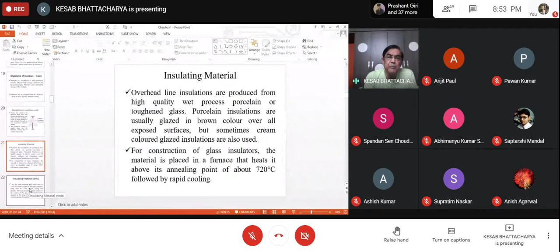And due to this process, heating it up to its annealing point and then rapidly cooling it, the material gets enough strength at the outer surfaces. The inside surfaces of the glass contract more than the outer surface during this process, and as a result, compressive stresses in the surface of the glass are balanced by tensile stresses in the body of the glass, improving the mechanical and thermal property of the insulating material. That way, the glass insulators have better mechanical and thermal properties than the porcelain insulators.